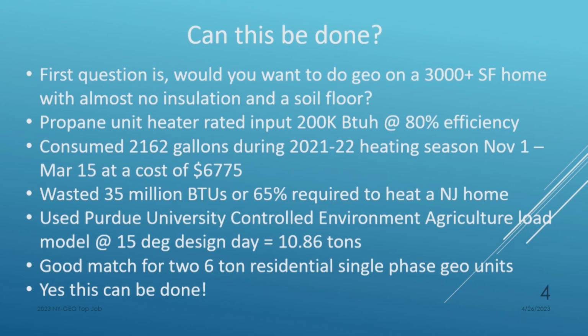Because of the grant and the grant timetable, they wanted to do growing in the 2021-22 season, so they went ahead and put what they call a unit propane furnace in. You've probably seen these things. They hang from the ceiling. They just blow hot air out. They have a flue that goes out the side, which loses a ton of heat. Basically, it's 80% efficient, so they're losing, we calculated, 35 million BTUs just out the flue. Enough to heat an average home 65% of the year.